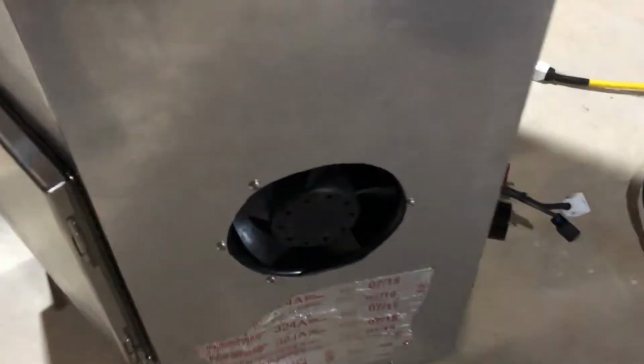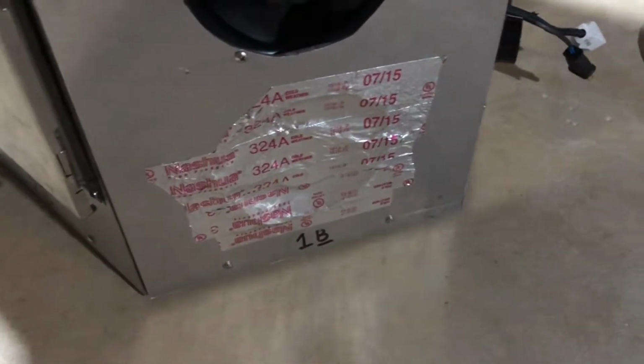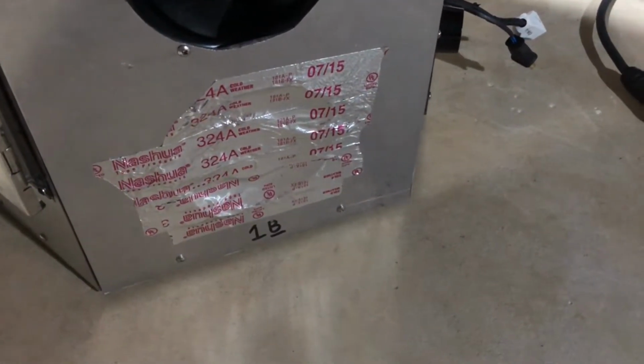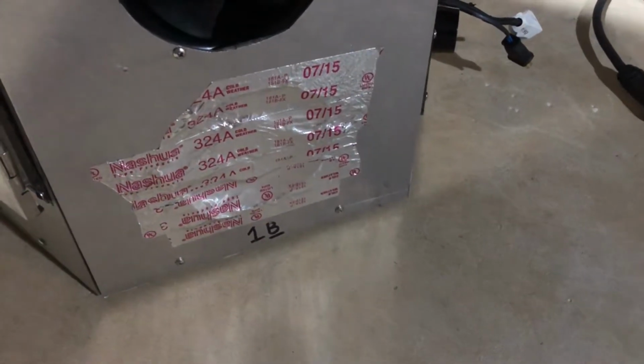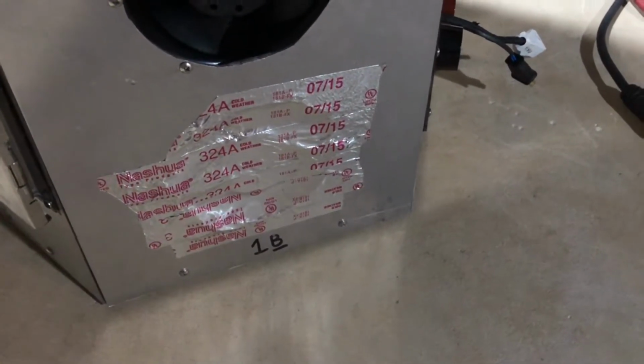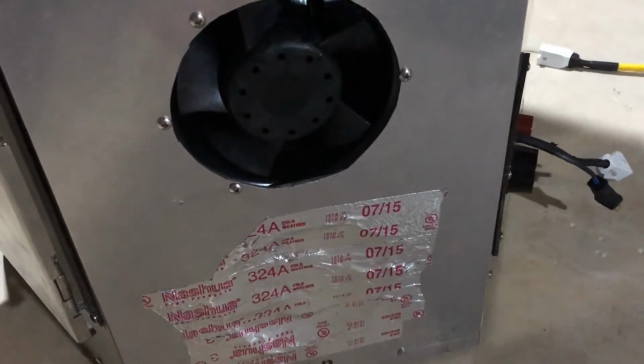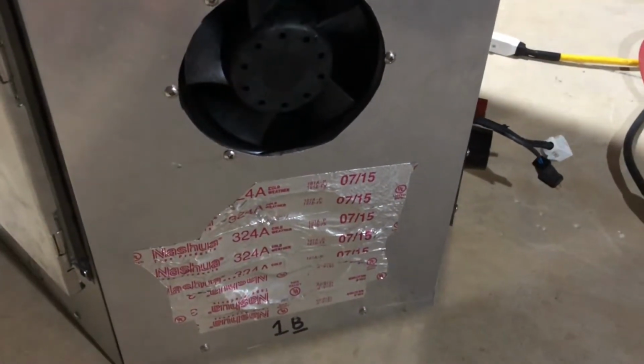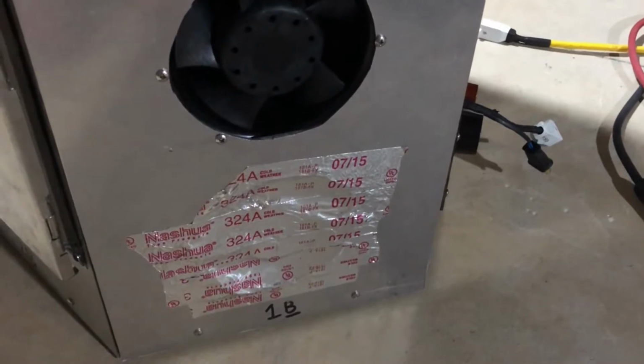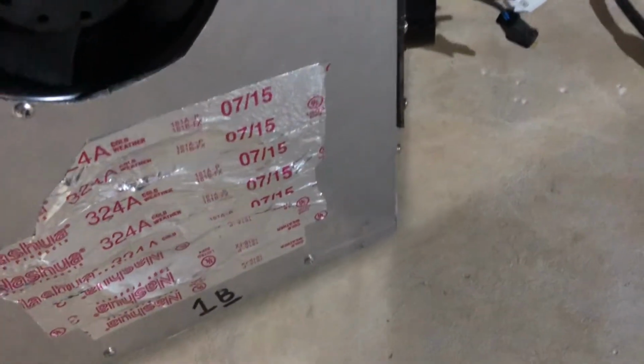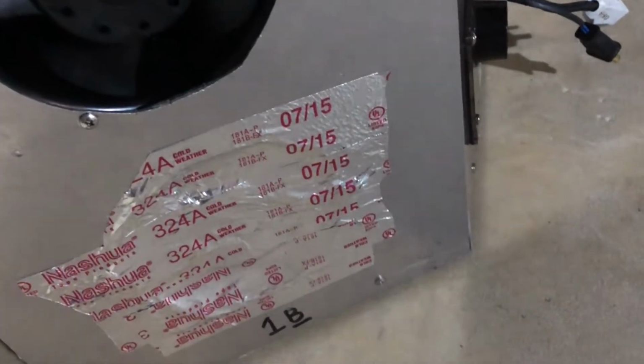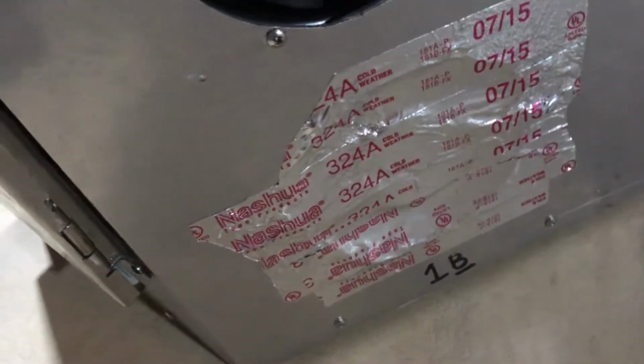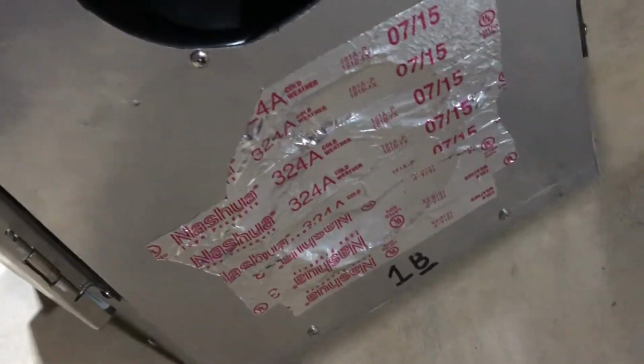This is the other main pressurization fan. I had another fan that I originally installed in here, but the issue was that it actually wasn't powerful enough. It was a different model number than these other 2 fans, and when these 2 fans spun up, the air started rushing back out through here, and it would start turning the fan in reverse, and it would overheat. So I ended up just disconnecting it and covering the hole up with some more duct tape.